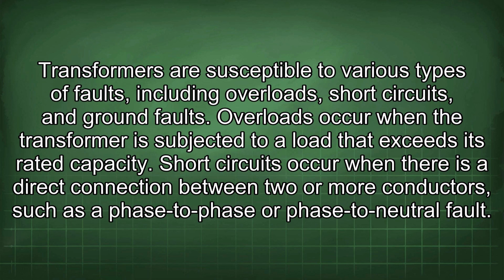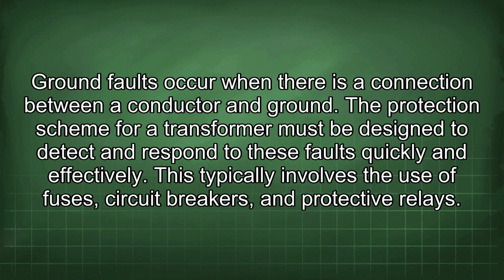Short circuits occur when there is a direct connection between two or more conductors, such as a phase-to-phase or phase-to-neutral fault. Ground faults occur when there is a connection between a conductor and ground. The protection scheme for a transformer must be designed to detect and respond to these faults quickly and effectively. This typically involves the use of fuses, circuit breakers, and protective relays.